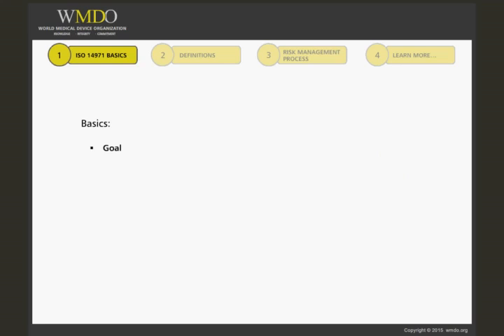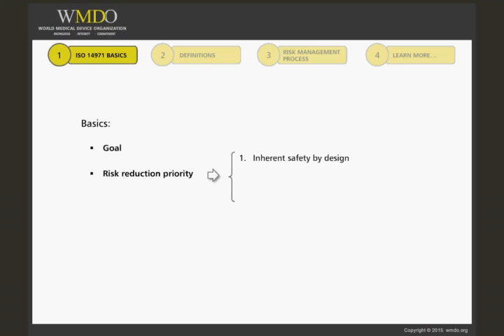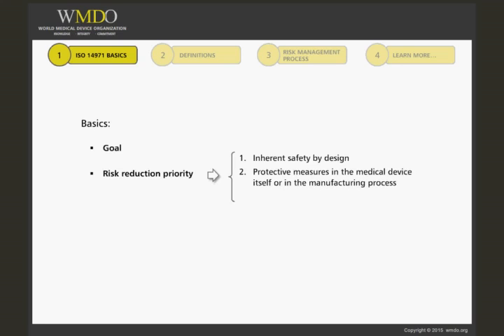Working towards this goal, the following order of risk reduction priority should be followed. First, try to make your device as inherently safe as possible — ideally, your device just can't fail. Second, as necessary, introduce protective measures to your device. For example, add an alarm function to warn in case of significant air leakage when using an emergency ventilator.